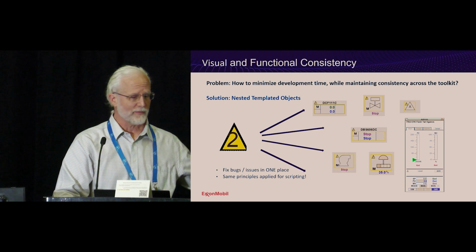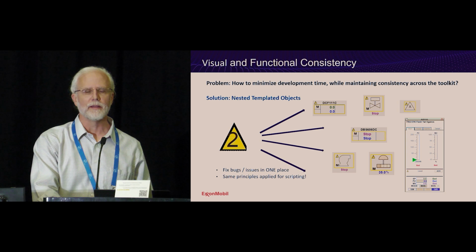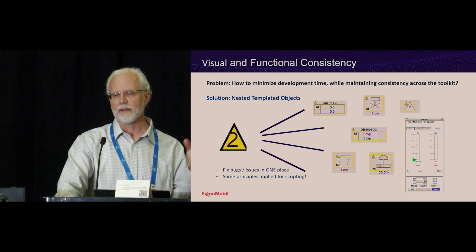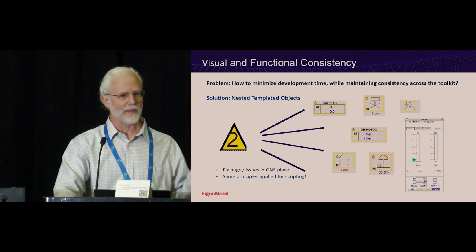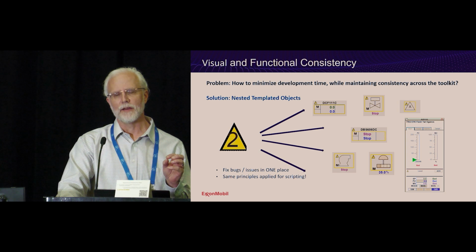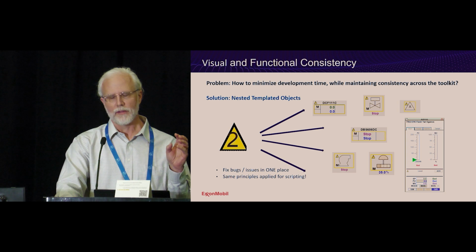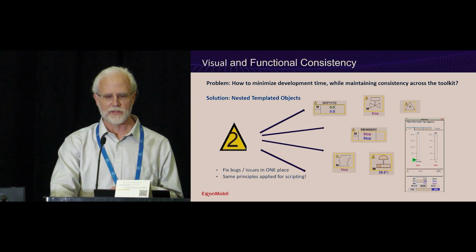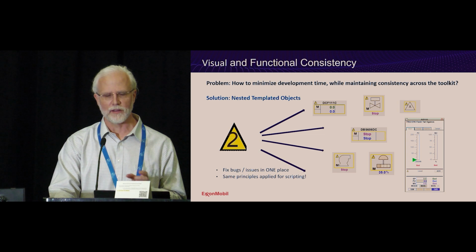On the left-hand side, you'll see there's a little alarm object, and that would appear when an alarm becomes active. Depending on the severity of the alarm, the look, shape, and behavior of that would be different. But that's an independent object that's now utilized in all of the higher-level objects in the displays. Whether that's being put on a controller shape, a valve shape, whether it's analog or digital, that same object is embedded in all of the other objects all the way.